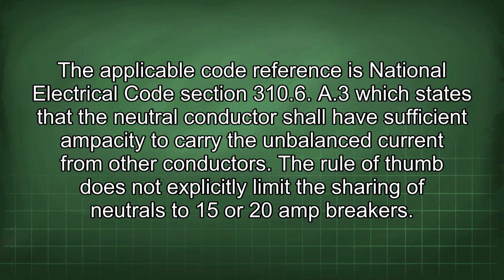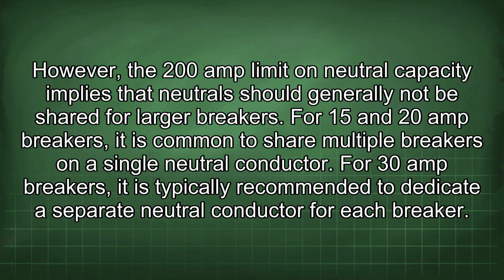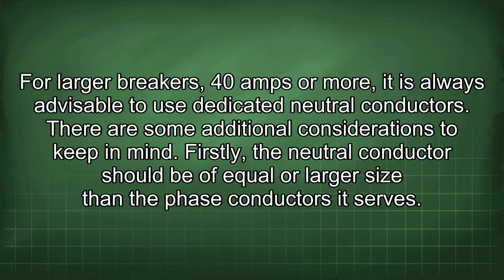The rule of thumb does not explicitly limit the sharing of neutrals to 15 or 20 amp breakers. However, the 200 amp limit on neutral capacity implies that neutrals should generally not be shared for larger breakers. For 15 and 20 amp breakers, it is common to share multiple breakers on a single neutral conductor. For 30 amp breakers, it is typically recommended to dedicate a separate neutral conductor for each breaker. For larger breakers, 40 amps or more, it is always advisable to use dedicated neutral conductors.